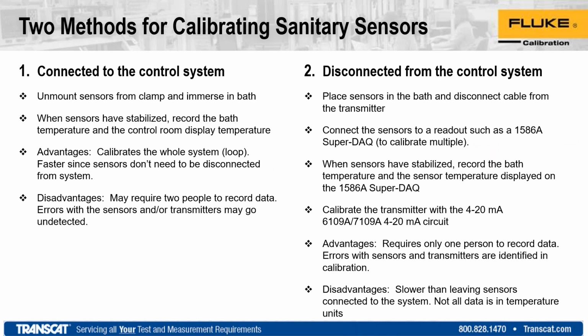All right, we're going to talk about two methods of using these products for calibrating the different sensors. One is where they leave the actual TriClamp connected to the system, or the control room, as some folks will call it. The second we'll discuss is disconnecting it. And there's actually kind of twofold on the disconnected one. We're going to talk about a sensor, and then also a transmitter, like a 4 to 20 milliamp.